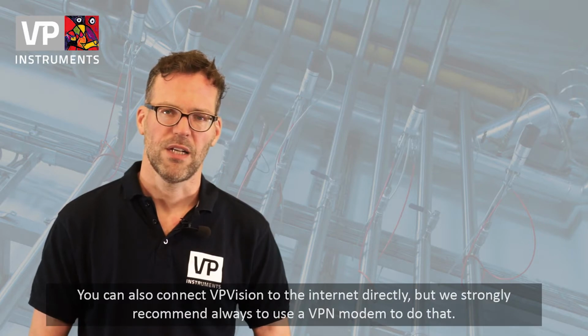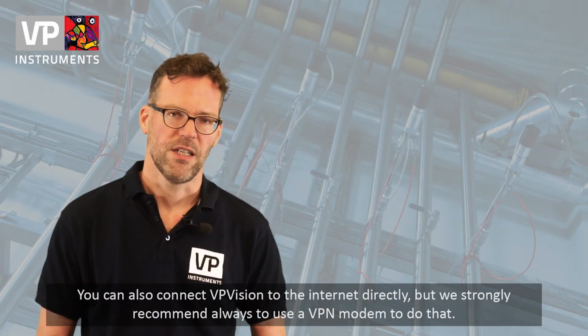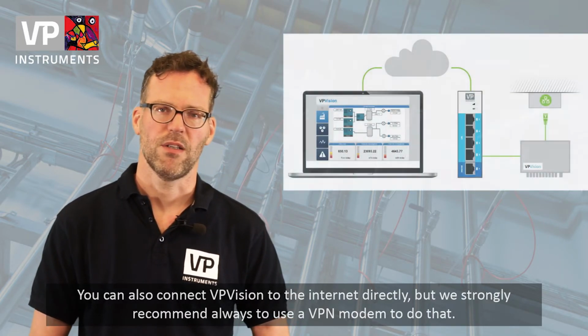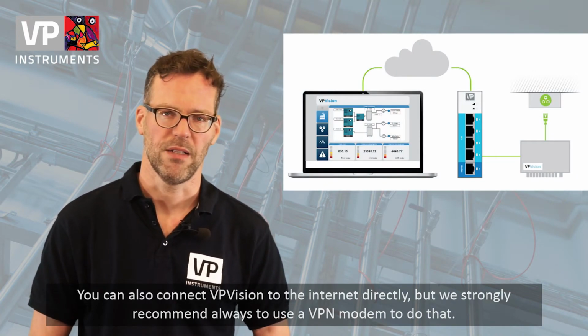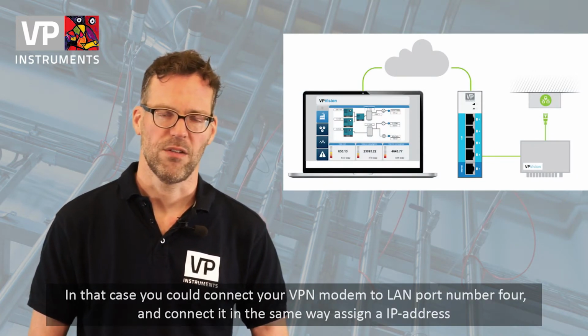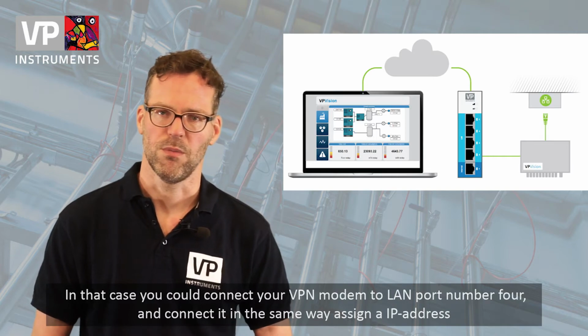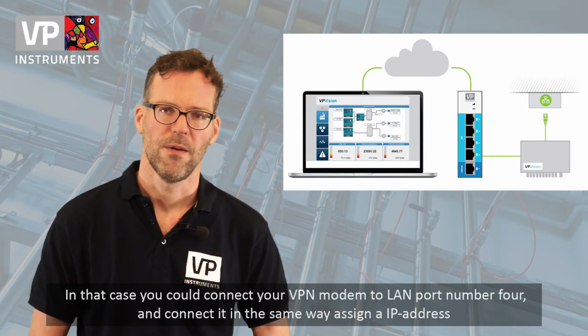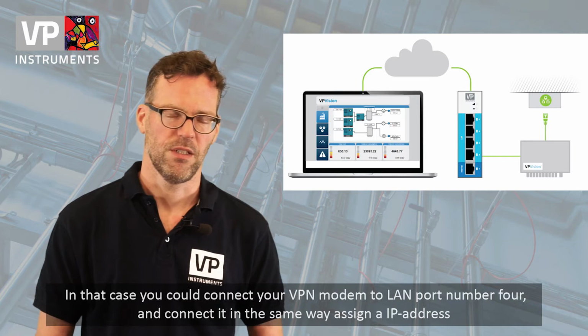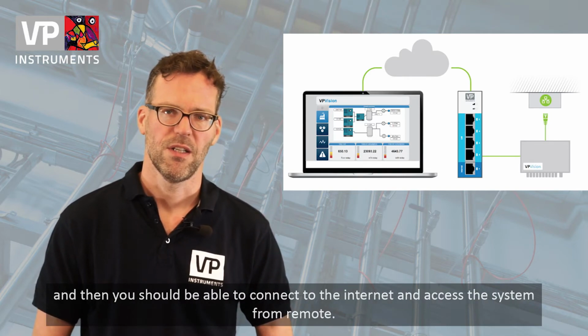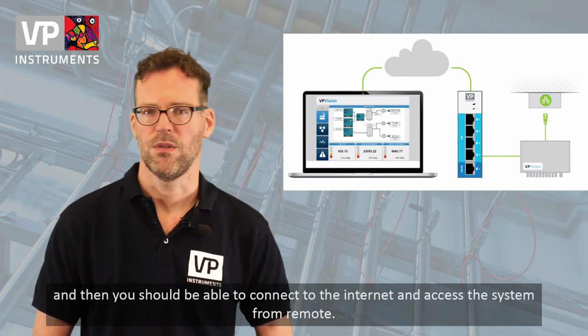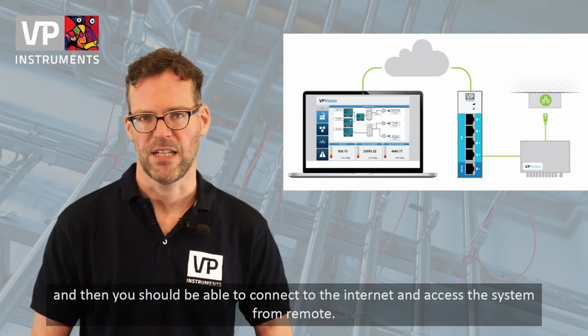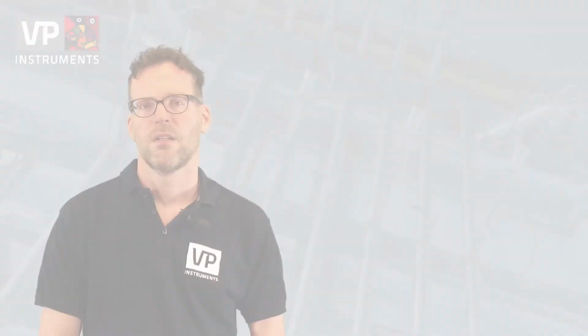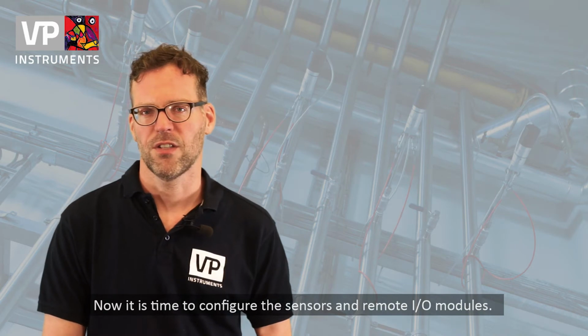You can also connect VPVision to the internet directly, but we strongly recommend always to use a VPN modem to do that. In that case you could connect your VPN modem to LAN port number 4 and connect it in the same way, assign an IP address and then you should be able to connect to the internet and access the system from remote. So now it's time to configure the sensors and the remote I/O modules.